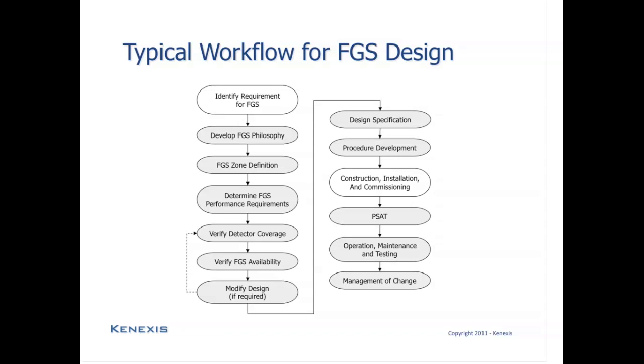In the typical workflow, you'll begin with a requirement for fire and gas system design. So coming into this flow chart, there will have been some sort of trigger that would require an engineering team or process design team to consider the need for fire and gas system design. This might be as the result of regulatory requirements. This might be as the result of design procedures from an operating company or an engineering company. It might be the result of a process hazards analysis or a PHA HAZOP perhaps recommendation. Or it could even be something like the recommendation of an insurance auditor or a regulatory body audit. If for whatever reason there has been a request to analyze the design of the fire and gas detection and suppression systems, you'll start into this workflow.